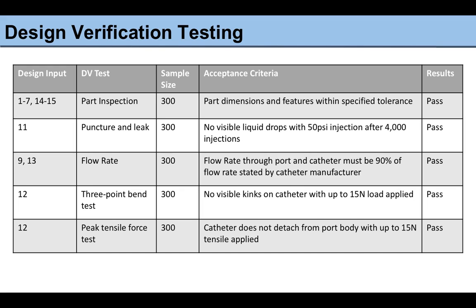All of our tests correlate to design inputs, showing that all of our design inputs are met with the device. The first set of testing performed was the design verification testing. This included 5 different tests. All of these tests had a sample size of 300 because they're all attribute tests.